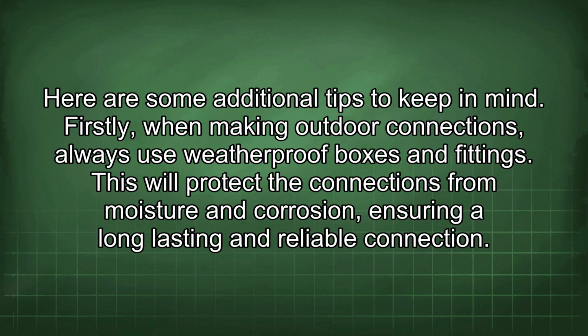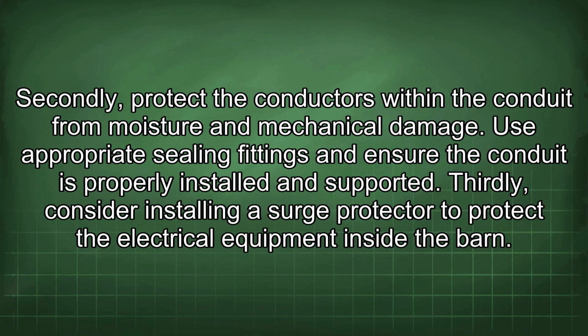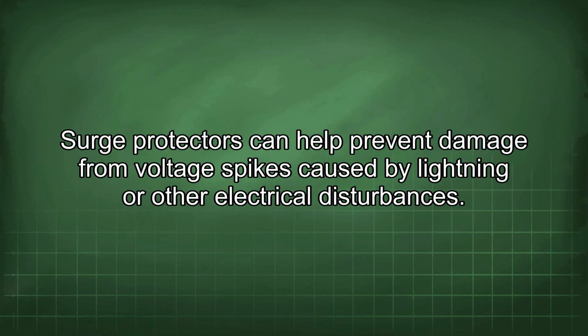Here are some additional tips to keep in mind. Firstly, when making outdoor connections, always use weatherproof boxes and fittings. This will protect the connections from moisture and corrosion, ensuring a long-lasting and reliable connection. Secondly, protect the conductors within the conduit from moisture and mechanical damage. Use appropriate sealing fittings and ensure the conduit is properly installed and supported. Thirdly, consider installing a surge protector to protect the electrical equipment inside the barn. Surge protectors can help prevent damage from voltage spikes caused by lightning or other electrical disturbances.